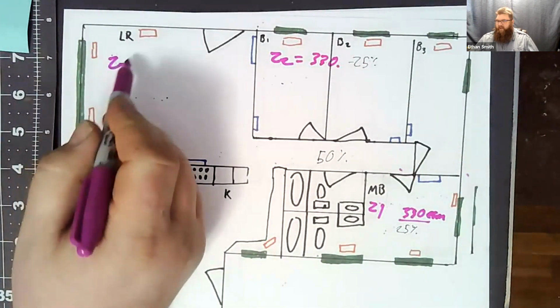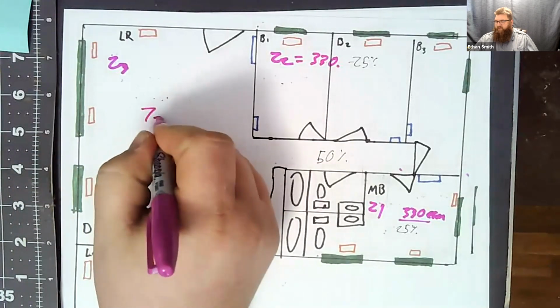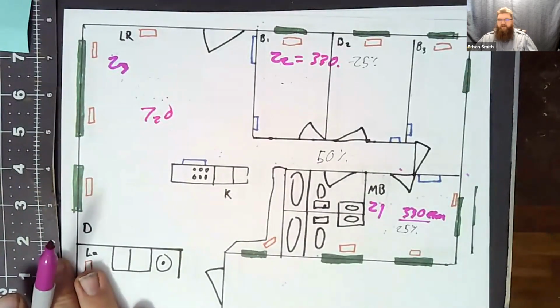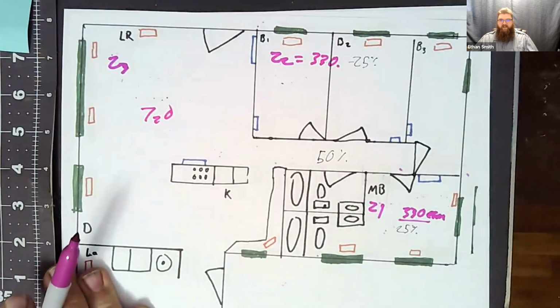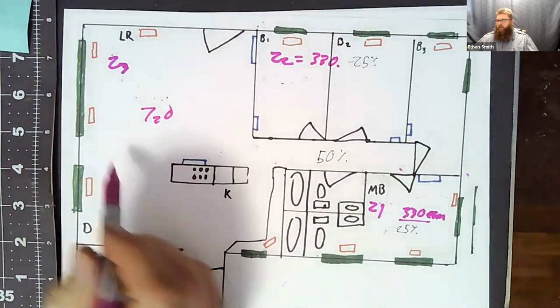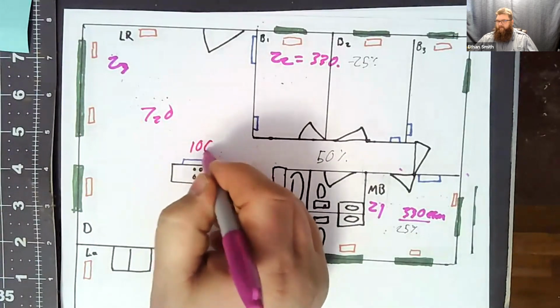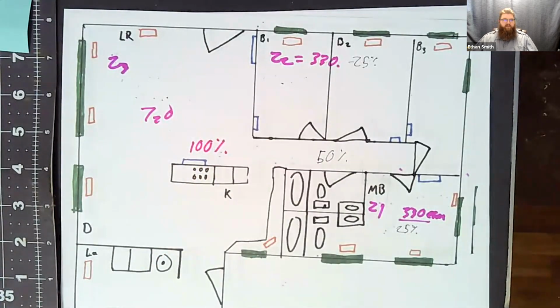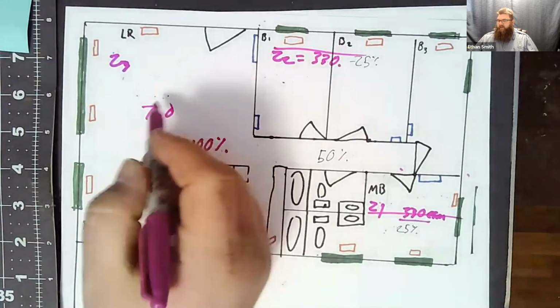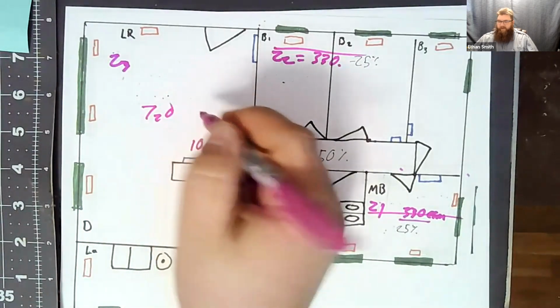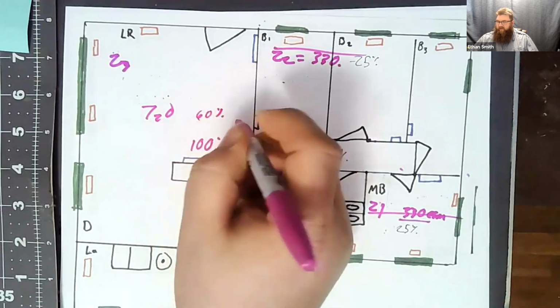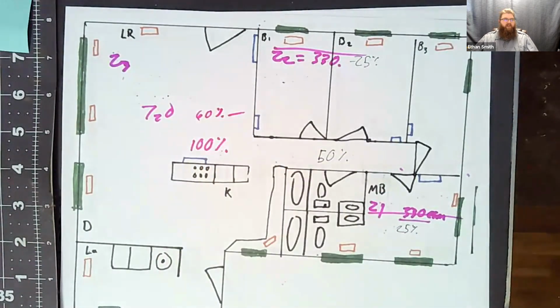I add my zone 3 to that, and 720 CFM plus 660 CFM is obviously more than the capacity of my outdoor unit. So it's going to take that whole system up to 100% at that point, deliver air everywhere. But then if my zone 2 drops off or my zone 1 drops off, it'll simply take me back down to about 60% and continue to run without any excess air. Okay.